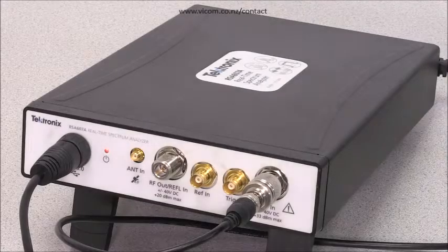And this quick how-to video will talk about how to use the RSA607A Real-Time Spectrum Analyzer controlled from a PC to conduct wireless LAN parametric RF testing for the physical layer test, testing against the IEEE 802.11 standards. So these kinds of tests are often done in both the R&D phases, design validation, and manufacturing test of wireless LAN modules, or maybe even semiconductor components to those modules. And then sometimes they may also be done in integration of the wireless LAN module to a larger device.